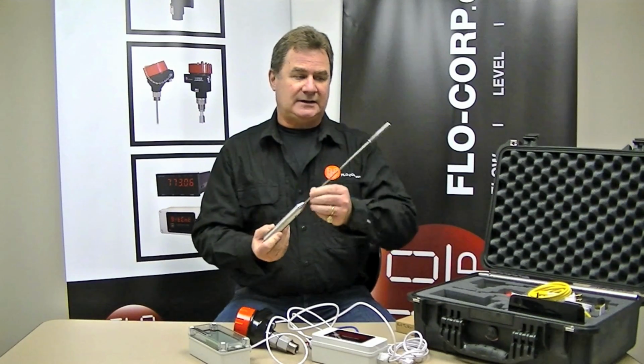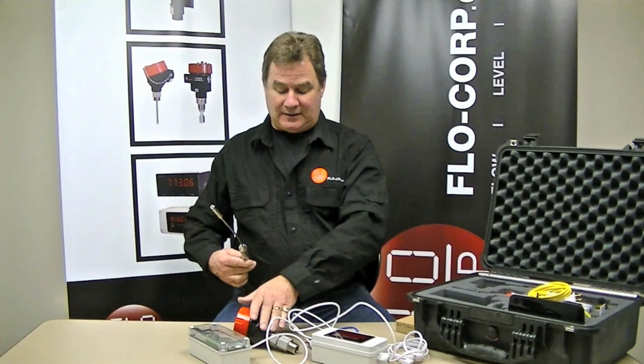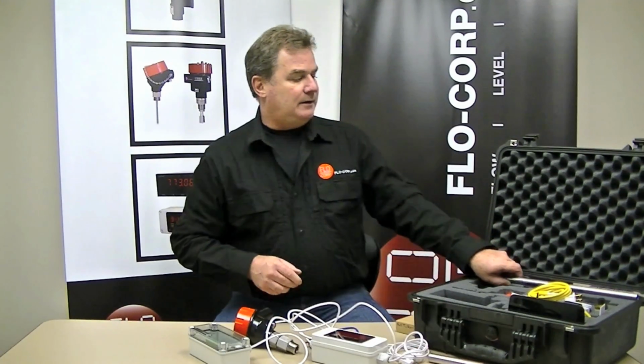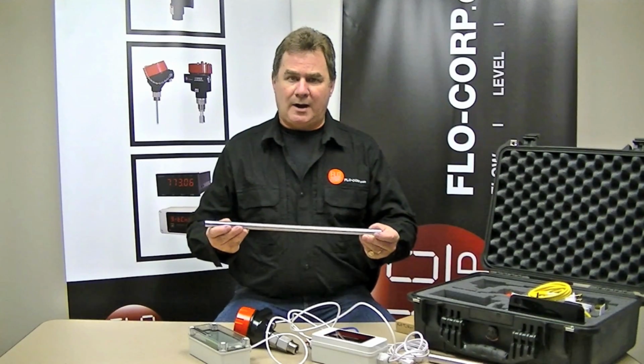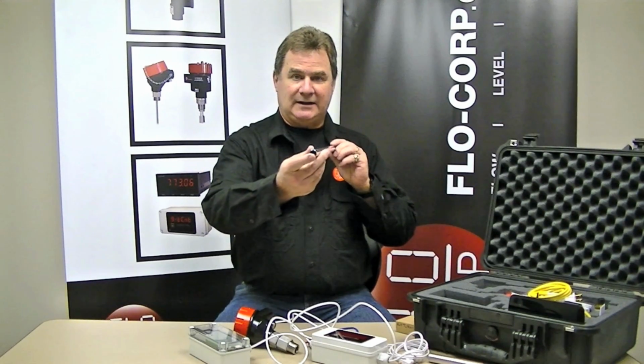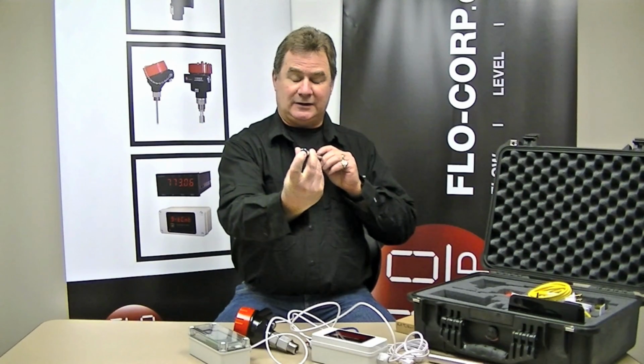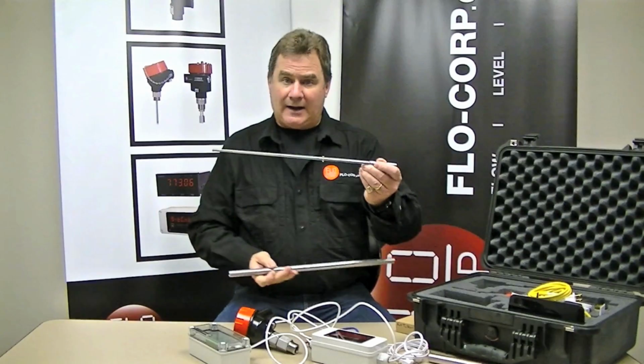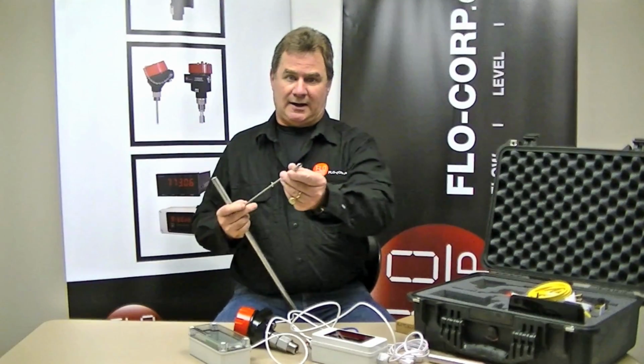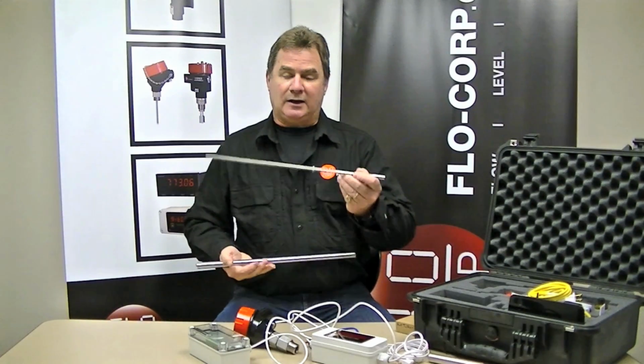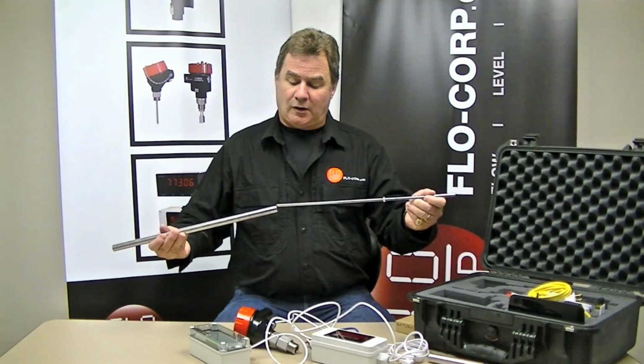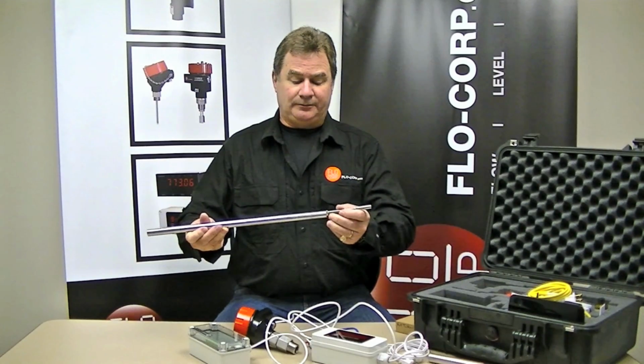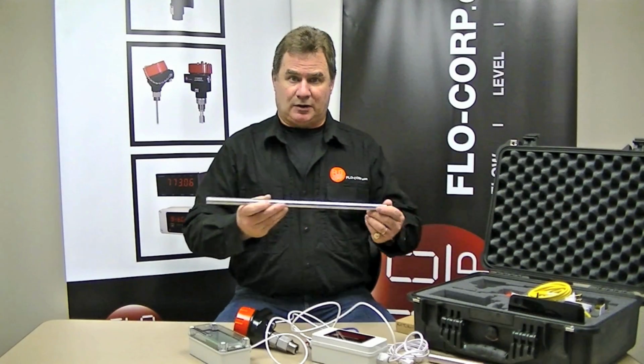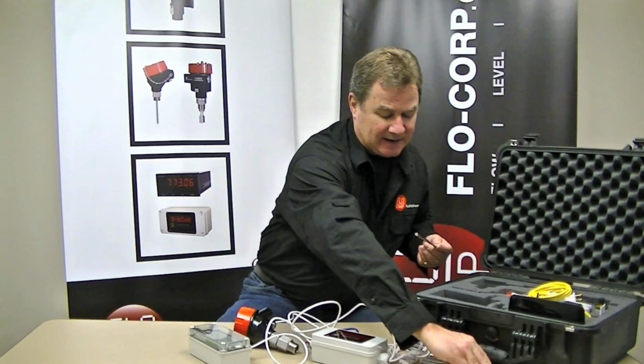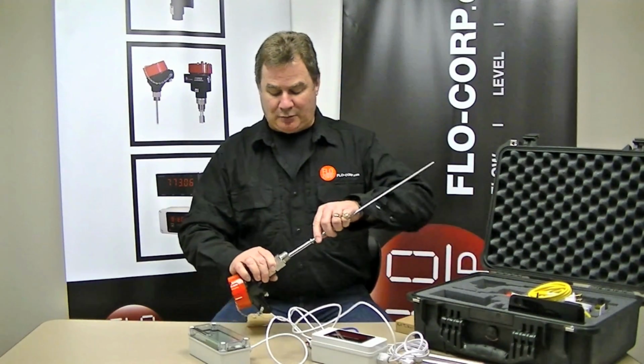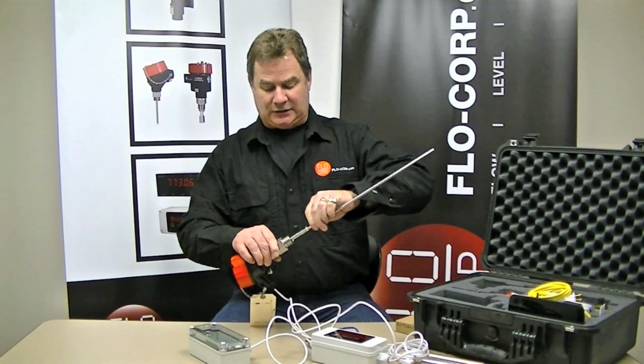It has a weight on one end, stainless steel cable, and it has the threaded connection that would thread up into the head. The other two probe options are a coax probe and a rod probe. The coax probe is a 1/2 inch stainless steel tube and it has a rod inserted down the center of it. The rod is a standard stainless steel rod, again with the threaded connection on one end. It could be used standalone as a rod probe, or when inserted into the 1/2 inch stainless steel tubing, now we've made this a coax probe. I'll set the stainless steel tubing aside for a moment and just thread the rod probe into the tracer probe connection.